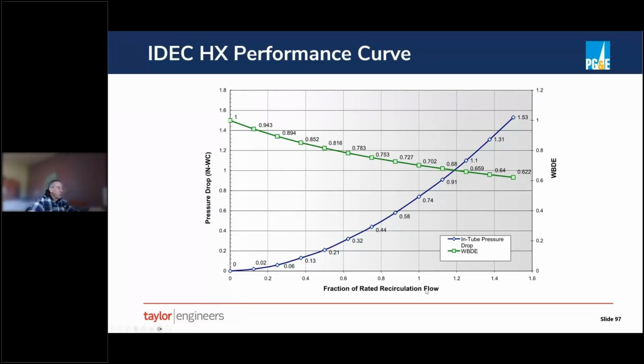What's the recirculated flow rate? And it's also showing the pressure drop. And so the pressure drop goes down very quickly as the flow rate goes down. And the effectiveness also goes up as the pressure drop goes down. With data centers, you almost always have redundant units and you're often not at full load. So it's very common to be operating at, say, 20, 30% flow per air handler. And then you're operating at a very low pressure drop through your heat exchanger, a very high effectiveness. So the system efficiency gets really good at part load.